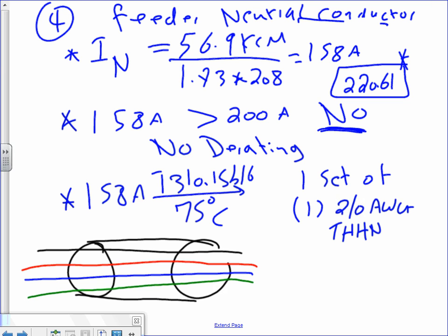If you go to 220.61, it will tell you if your neutral is more than 200, what do you do with that? The portion that's more than 200, you guys remember? The portion that's more than 200 in the neutral, you cut it 70%, right? So I verified that's not more than 200 here. Because if it was, Brandon, what would you do? The portion that's more than 200, cut it by 70%.